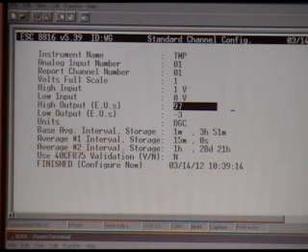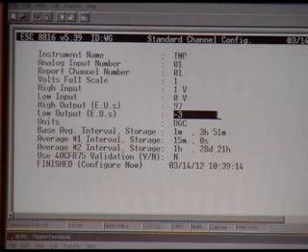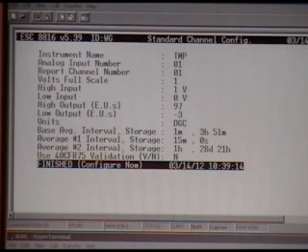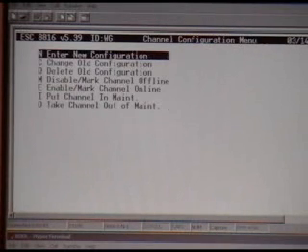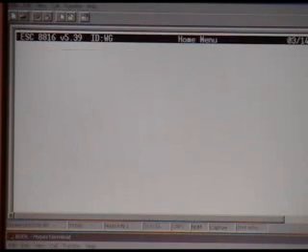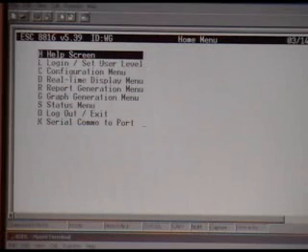I shifted it down 1. Instead of 98 and -2, I made it 97 and -3, which brought it down about a degree and made it jive a little bit better with our NIST standard. Having made those changes, you have to scroll down to Finish Configure Now, and hit Enter. And it would record and save those changes. And it will just come right back out.